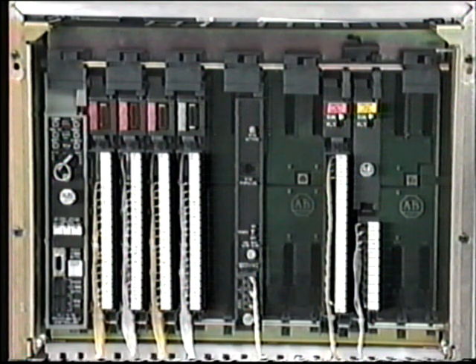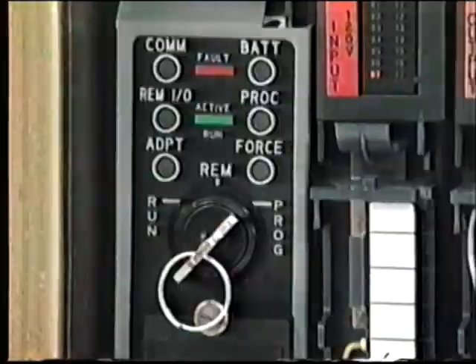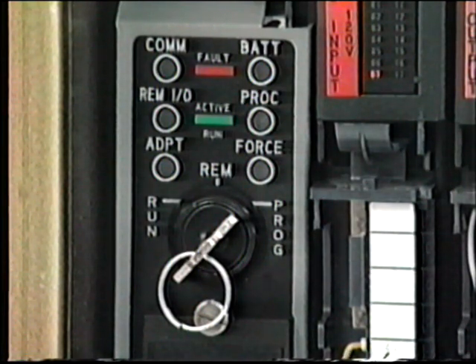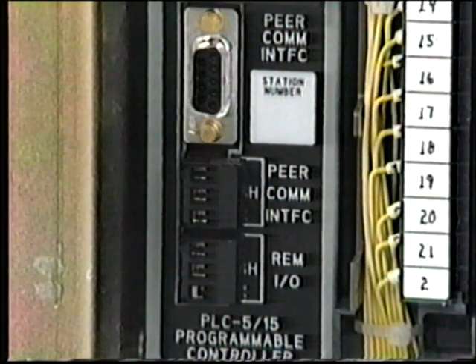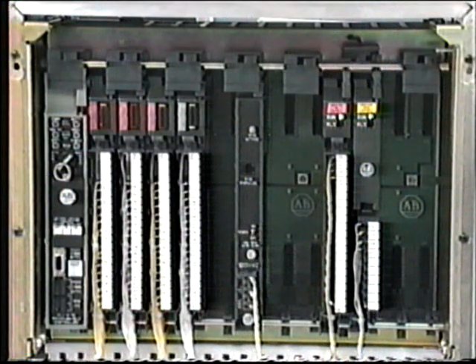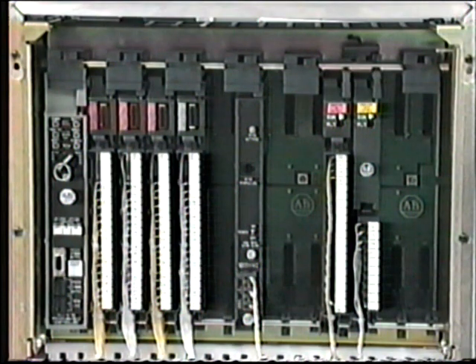For more complex control schemes, a rack-type PLC would be installed like this. This unit contains several different printed circuit modules which can be selected to suit the specific purpose. Typically, the modules would include several input and output cards, input and output control modules, cards for logic memory, logic control, and arithmetic control, a communications module for interconnection with other devices, a power supply. This module needs to provide power for both the PLC and its modules and must be selected with this in mind. This particular processor can handle up to a total of 512 inputs and outputs, so you can see that it has a fairly large capacity.